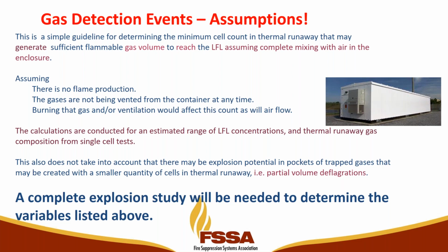Keep in mind there are a lot of assumptions done here. There is a method to do this evaluation, but you've got to figure out how to determine the failure mode. In these examples there's no flame production, gases are not being vented, there is some airflow, and we're looking at a range of LFLs. So there's a lot of assumptions here - you really need a complete explosion study to determine these variables and have a reasonable expectation of what failure looks like.